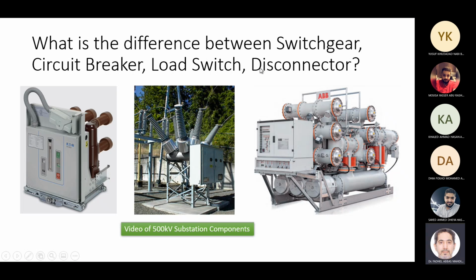While a disconnector is not designed even to break fault current, it is not designed to even sometimes break load currents. So it's not intended for switching. It is intended for the purpose of isolating a device. You want to isolate it.